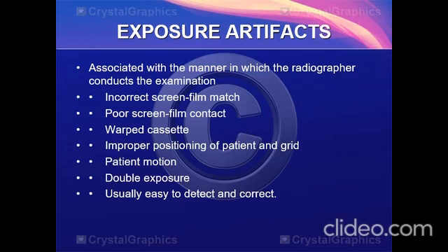So if we have remembered in our previous discussion, the screen film matching is very important. So the color of light emitted by the screen must match with the color of light in which the film is sensitive.